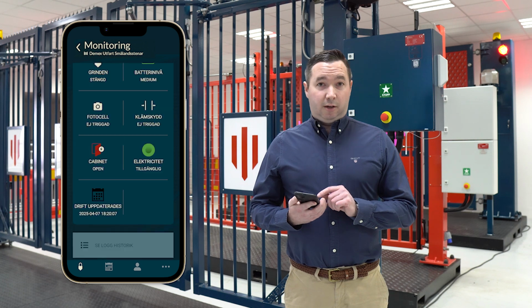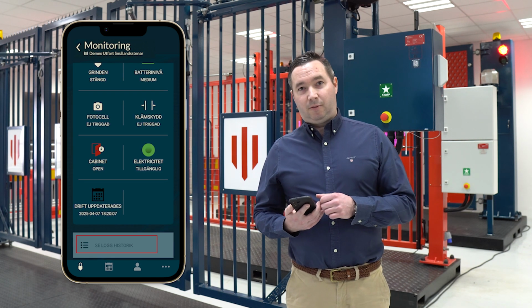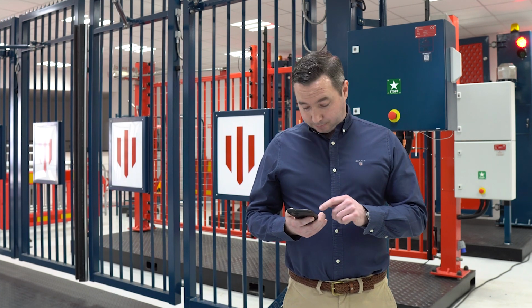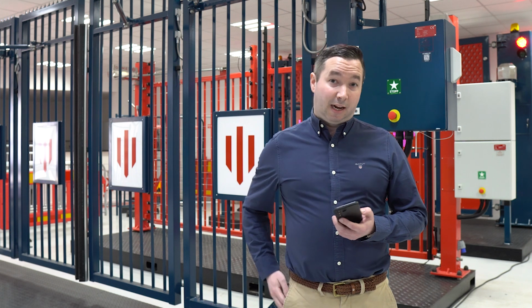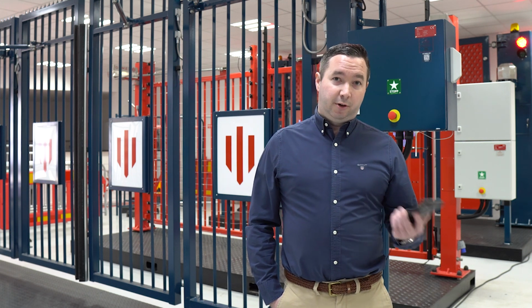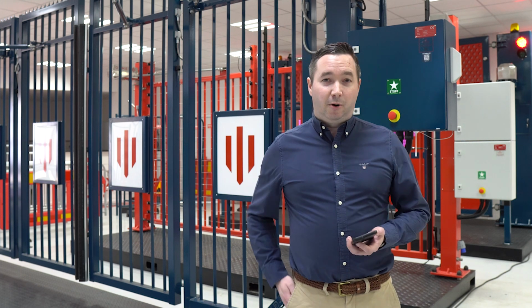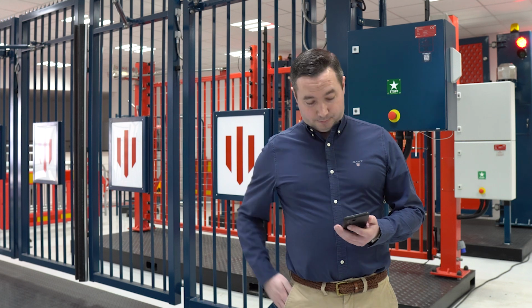You can also see the log. If you click on see log history, you will also see the log, what happened with the gate, how many times has it been opening, closing, and also if it's been a power cut. And we can also see if it's lost connection with the cloud before a power cut. That will then allow us to know if the power cut was before, and then we lost connection to the cloud. That would then mean that there's been a power failure at the site. Whereas if we lose the connection to the cloud at the same time as the power, we then know it's probably a connection problem. Maybe there is something with the cloud.